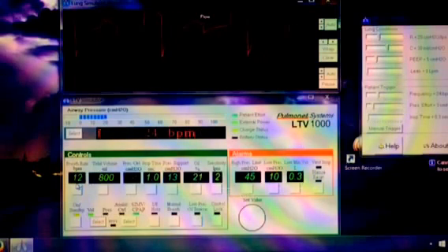Right now we're in the volume type breath. Two important settings we're going to talk about: the breath rate, also called the respiratory rate. Right now it's set at 12. That's the minimum amount of breaths that the ventilator will deliver per minute — those are mandatory breaths. The patient can take spontaneous breaths in between, but at the very least they'll get 12 breaths per minute.